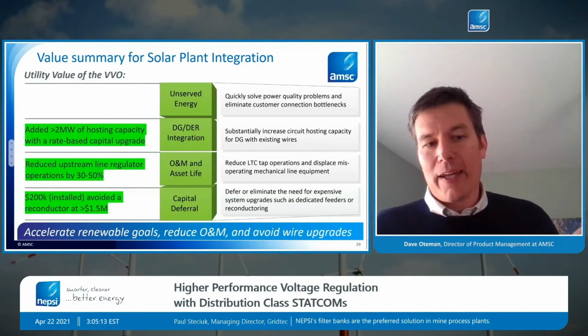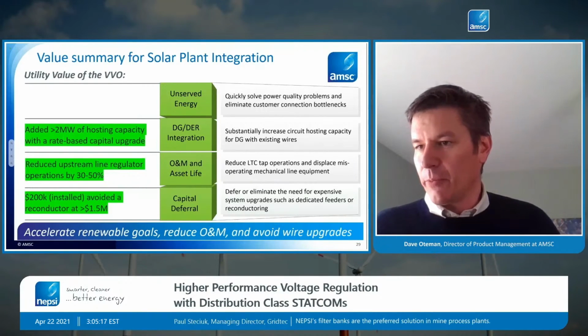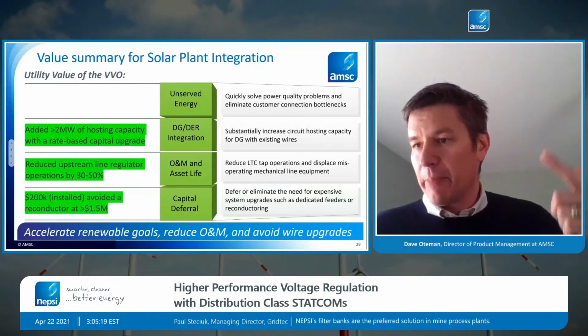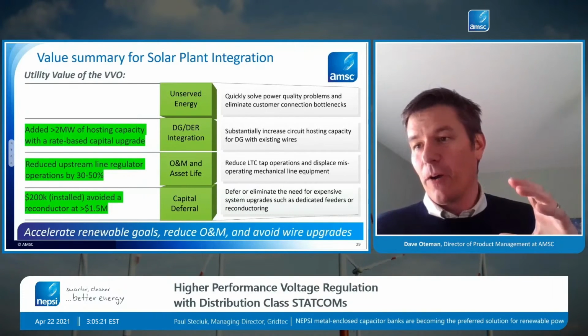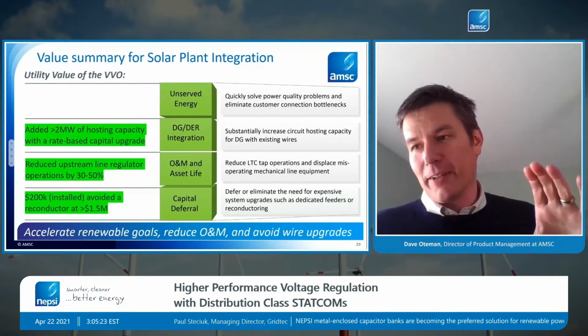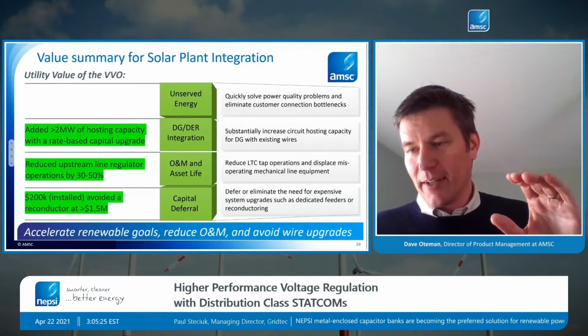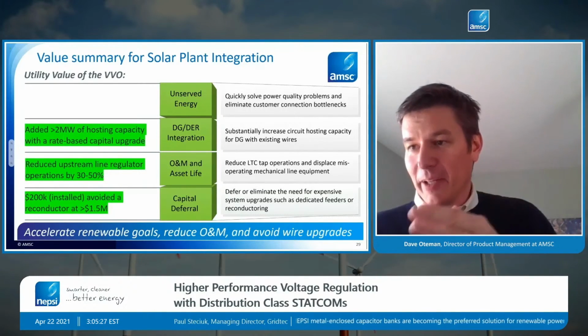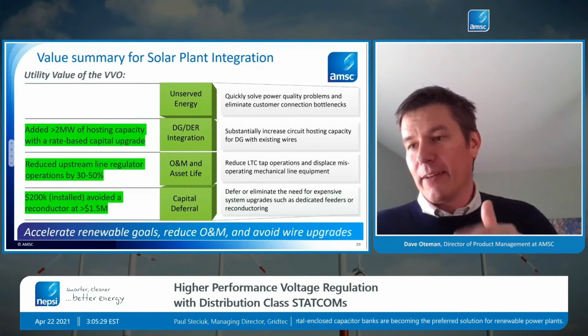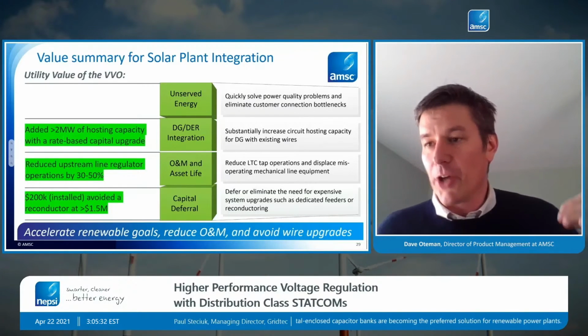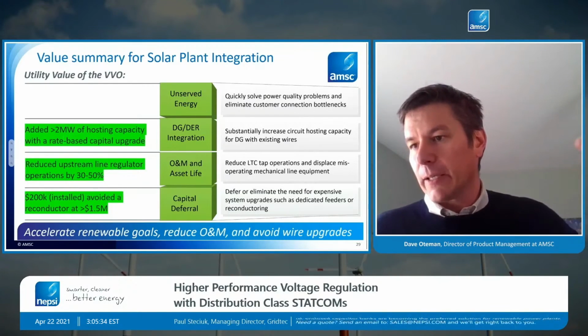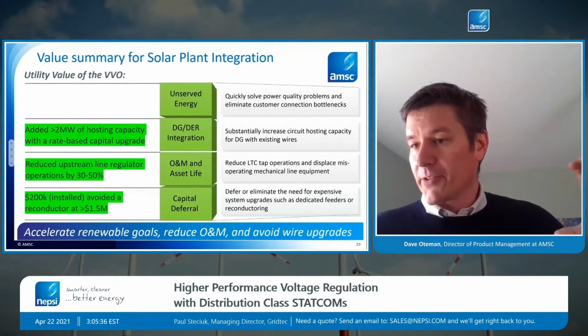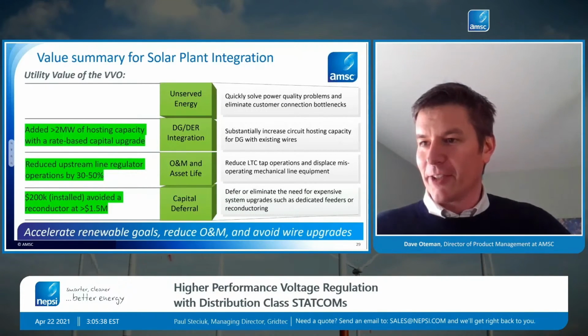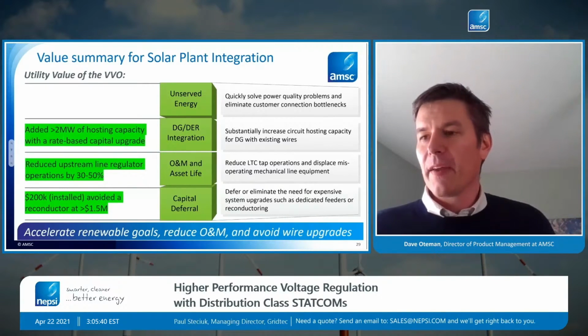It also reduced the operating load on the upstream regulator from the standpoint of tapping operations. Because the VVO is the primary voltage regulator on that portion of the circuit, it's regulating voltage very rapidly and precisely. Now the upstream devices don't have to respond as frequently, and they're able to just do the average voltage regulation they were intended to do.